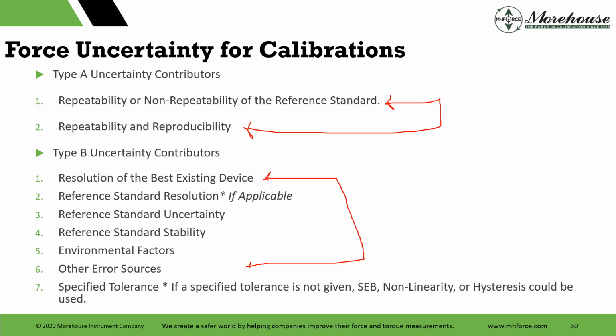If we look at other type B contributors: reference standard resolution, if applicable. If you're using dead weight, that's 0. If you're using a load cell, you would use the reference standard uncertainty. Where was my item calibrated? Remember, this is a big one. If the reference standard uncertainty is 0.002% of applied, like at Morehouse, your uncertainty cannot be any better than this. No way. You cannot be better than the reference standard uncertainty.